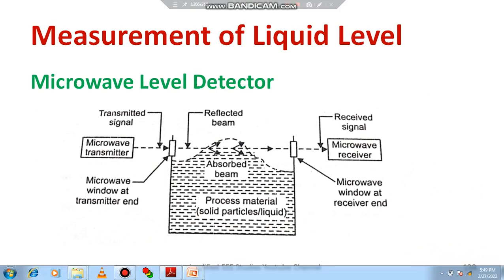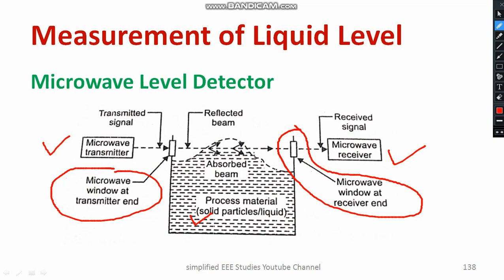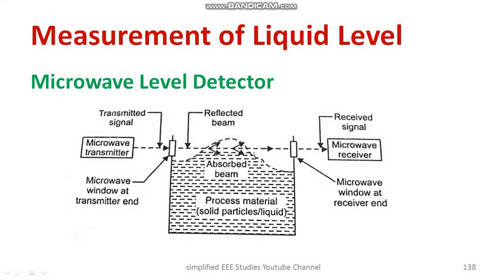Consider the diagram. Our ultimate target is to measure the liquid level of the process material, which may be solid particles or liquid. We have a microwave transmitter with a microwave source and a microwave receiver. A microwave window is required at both the transmitter end and the receiver end. The microwave beam is passed through the window at a desired frequency, and the time taken for the microwave to travel from the transmitter to the receiver is measured. If there is no liquid, it reaches very quickly; if there is liquid, it blocks the movement of the microwave, and the time duration is measured accordingly.